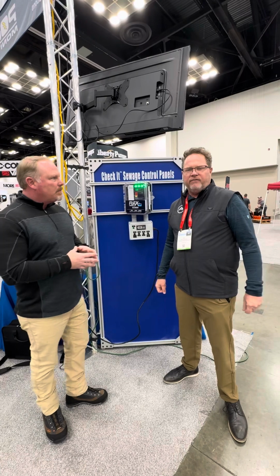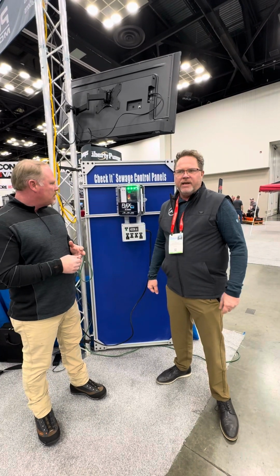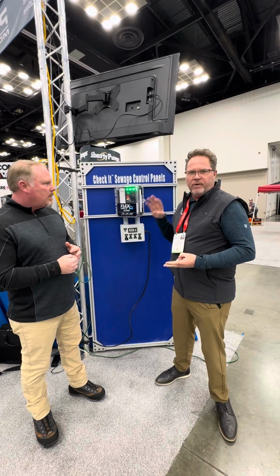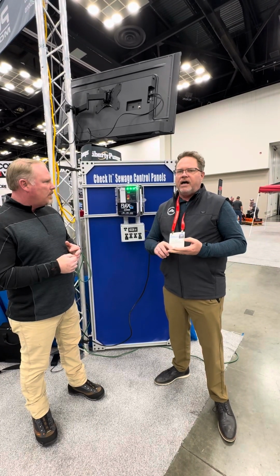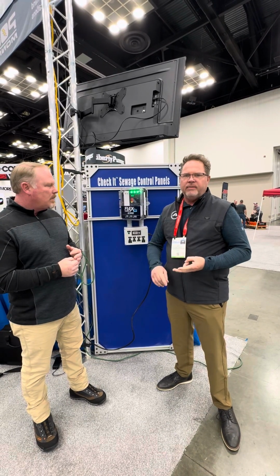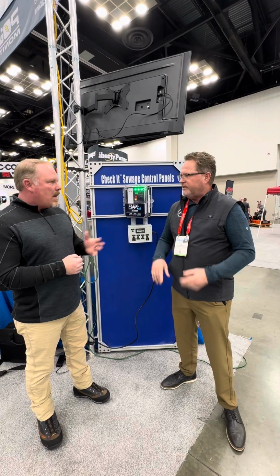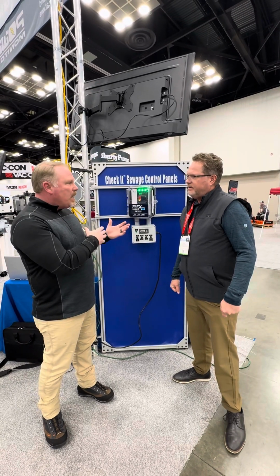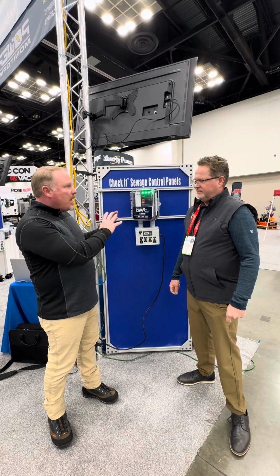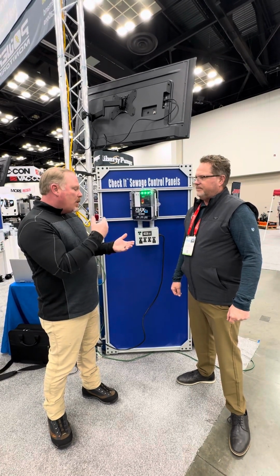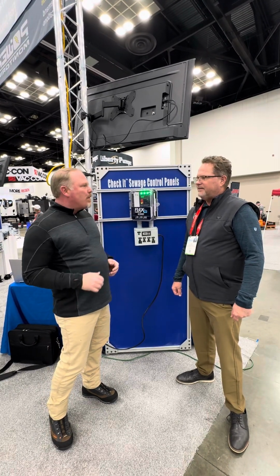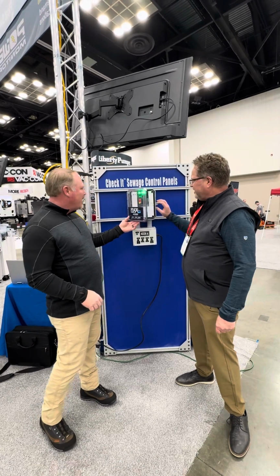Okay, we're going to be talking about our Flex control panel system that can be a demand dose or time dosing system. We're going to show you how you do that real quick. It also has a lot of data harvesting, meaning pump counters, pump lapse time, high water alarms, things like that. And not just the counters, but maybe the ability to understand what time those pump cycles were, how many, logging that data so we could go back and understand, do I have a leaking tank? Do I have a homeowner that's using too much water? Yeah. Or do I need to focus my attention on the drain? Exactly. Very good. So let's get at it.